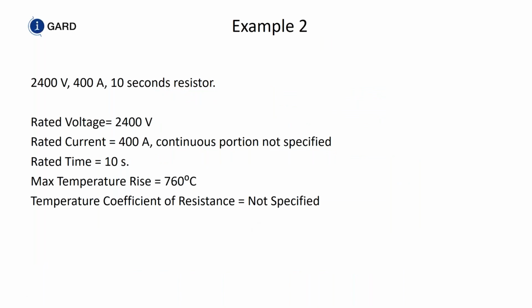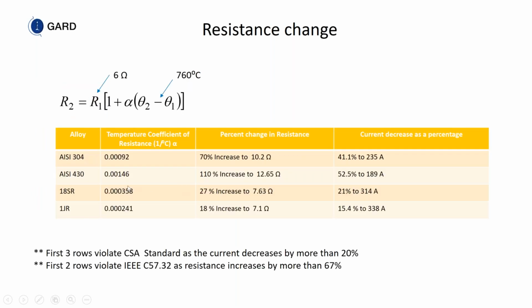Second example, you have a 2400 volt, 400 amp, 10 seconds. Now you would imagine 10 seconds is not continuous. It can't possibly change that much. 400 amp continuous portion is not specified, 10-second resistor, but the temperature rise increases to 760 degrees. Now with the same element, 6 ohms, 760 degrees C, with the 304 stainless steel, we went from 6 ohms to 10.2 ohms. We increased 70% from 6 ohms to 10.2 ohms.